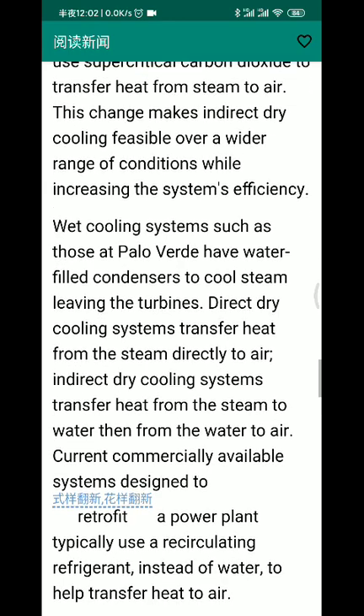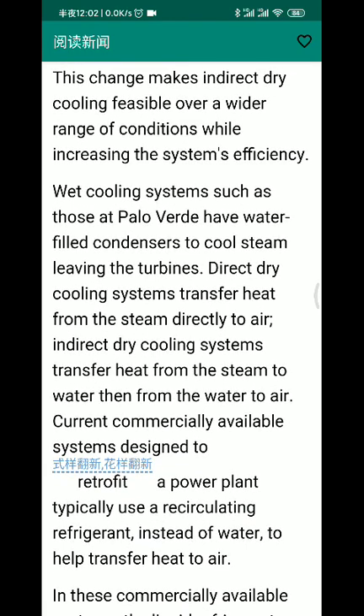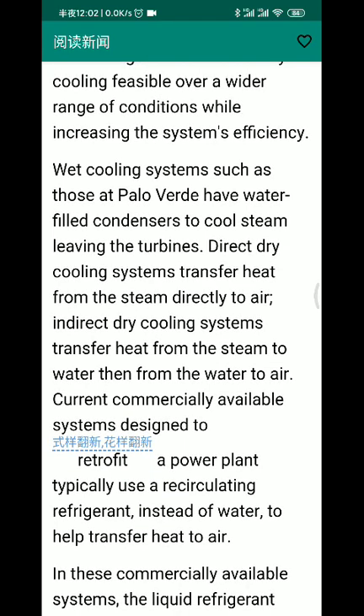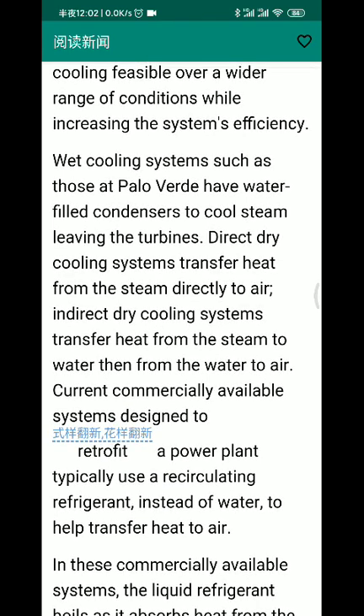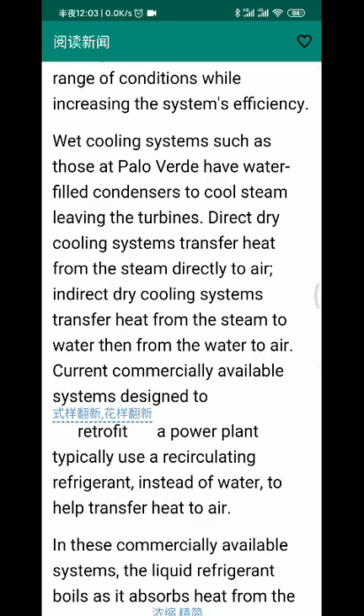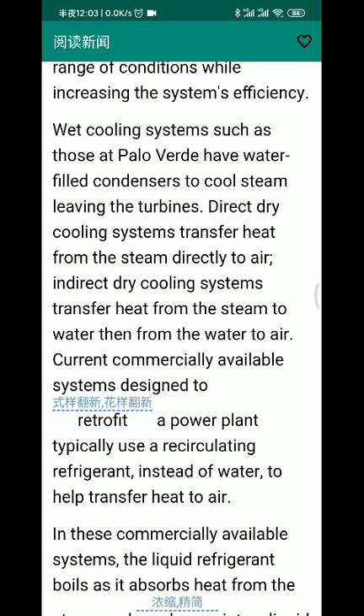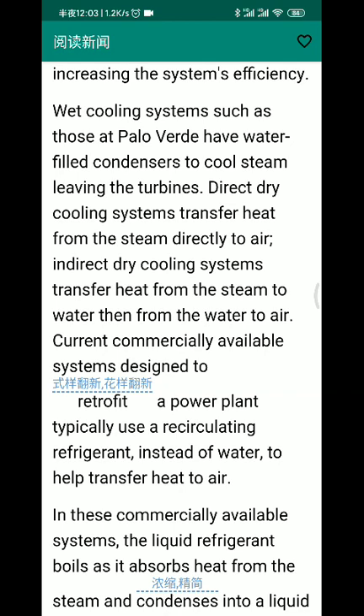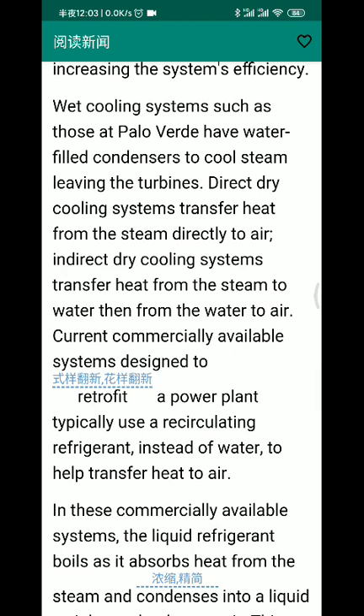Wet cooling systems, such as those at Palo Verde, have water-filled condensers to cool steam leaving the turbines. Direct dry cooling systems transfer heat from the steam directly to air. Indirect dry cooling systems transfer heat from steam to water, then from the water to air. Current commercially available systems designed to retrofit a power plant typically use recirculating refrigerants instead of water to help transfer heat to air.